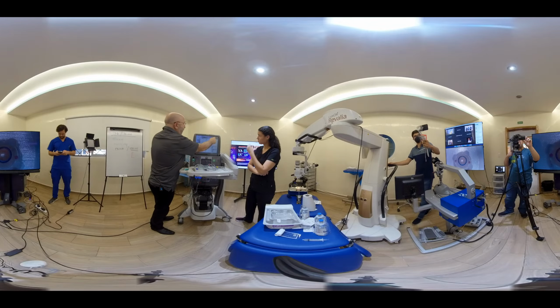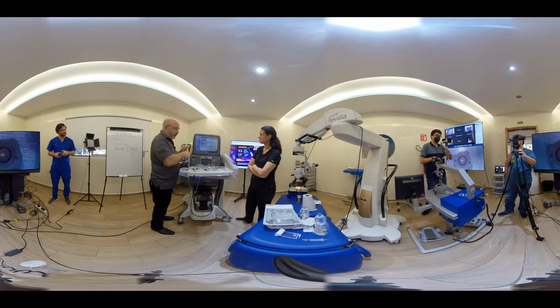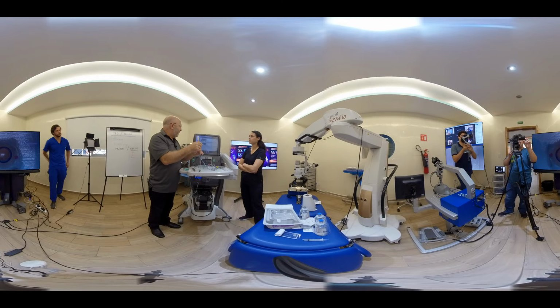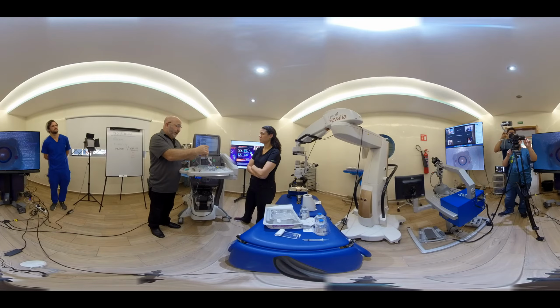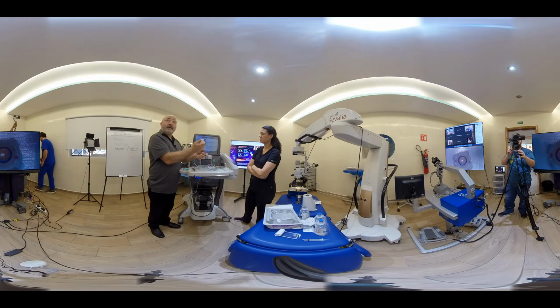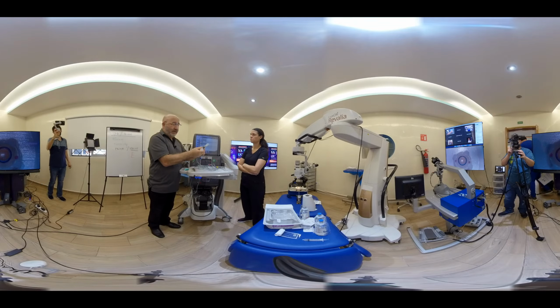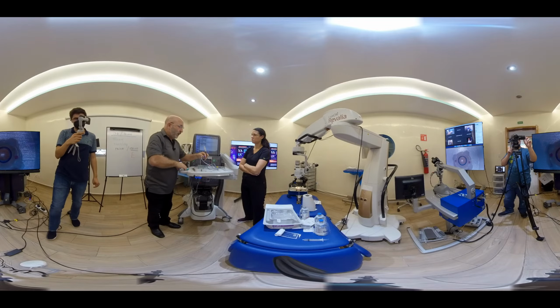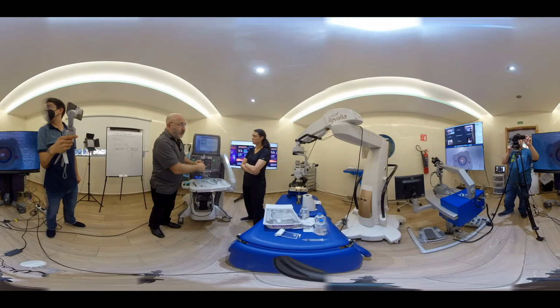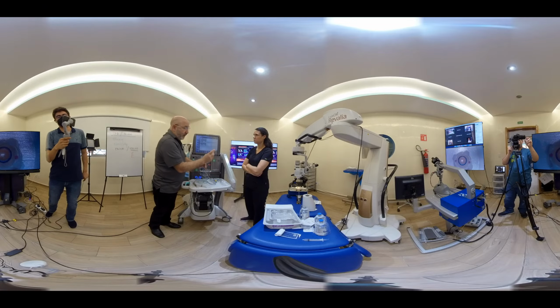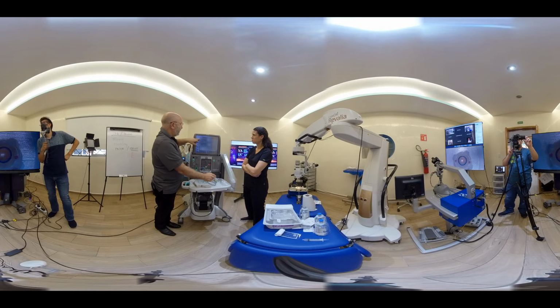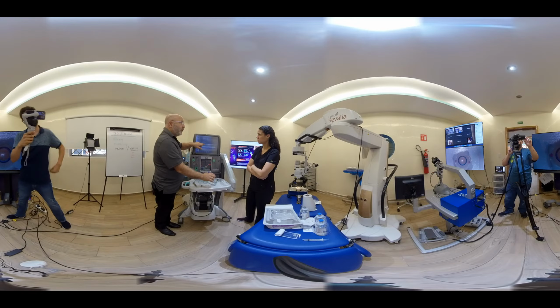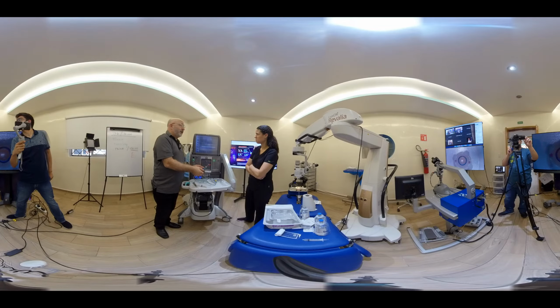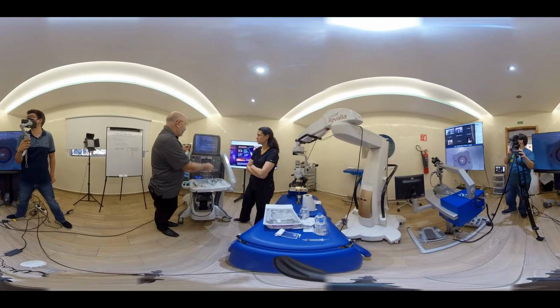Okay, we're here. We're in the surgical step, and we're going to do that sample. We don't have any fluid in here. So now you can have your colleague doing the suction while you hold the probe in the eye and run the cutter to extract your sample. Having done that, got your sample, you need to join this together. And now that this is primed and calibrated, I can put this back down again. We need to put this in a bowl, and I would use this protector, come up here where the probe is, and hit test instrument, and it won't start priming, it'll do a subprime until you press this little play button. When you do that, it'll now suck fluid up all the way back to the cassette, and then test the probe at that point. And then you'll have a fully primed system.